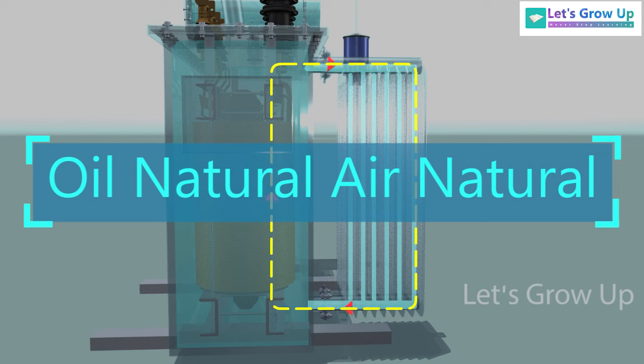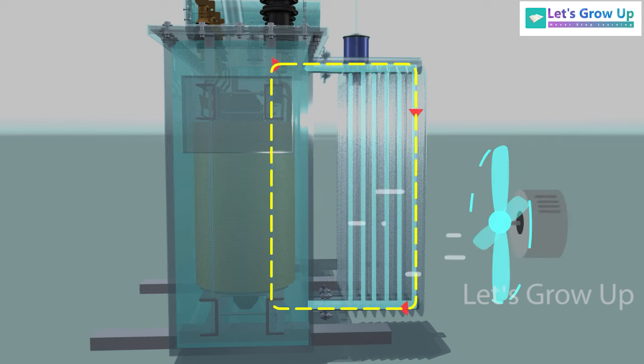In the large size transformer, the cooling process of radiator can get faster by the force of air, that means external fans are provided. This method is called oil natural air forced cooling.